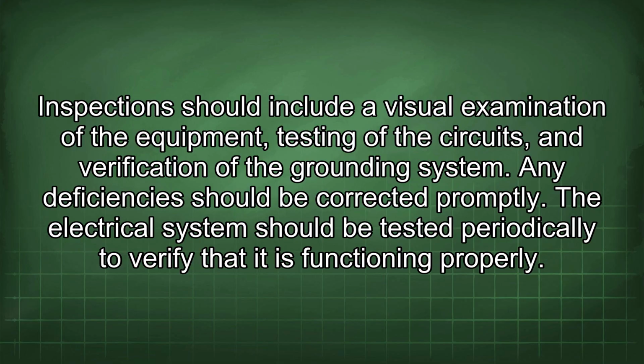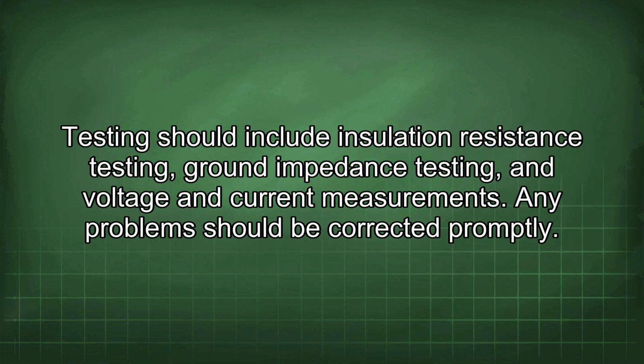The electrical system should be tested periodically to verify that it is functioning properly. Testing should include insulation resistance testing, ground impedance testing, and voltage and current measurements. Any problems should be corrected promptly.